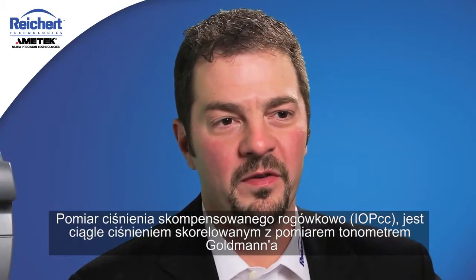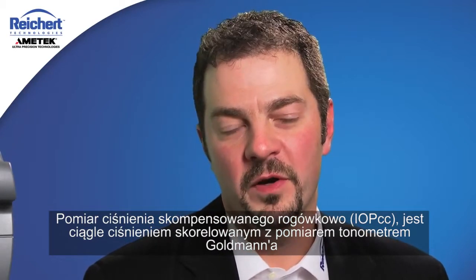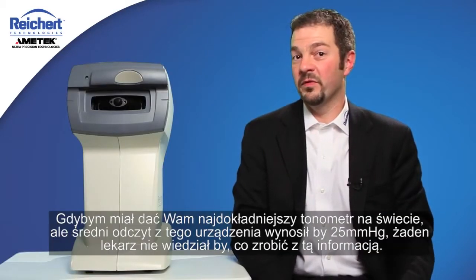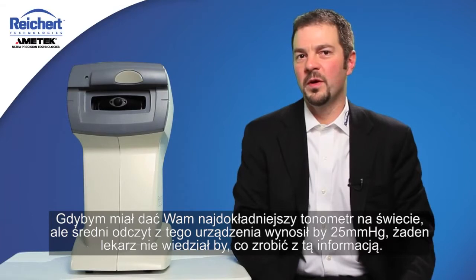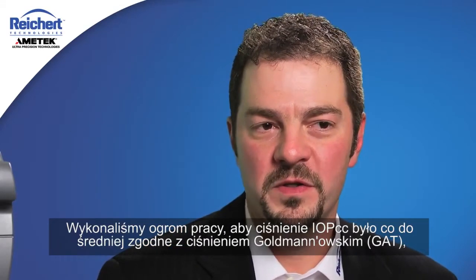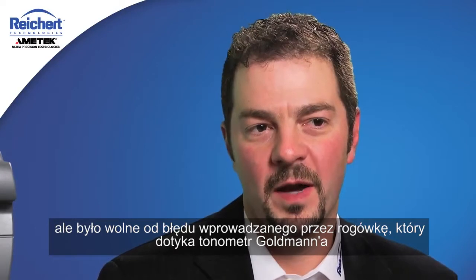The corneal compensated pressure measurement, IOPCC, is still a Goldmann correlated pressure measurement, and this is a very important point. If I were to give you a tonometer that was the most accurate in the world but the average reading was 25, no clinician would know what to do with that information. We went through painstaking efforts to make sure the IOPCC measurement still agrees with Goldmann on average, but lacks the corneal contamination that plagues Goldmann tonometry.